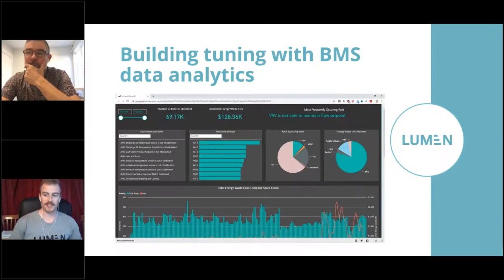In a slightly more complex case, the rule could ask, is the air temperature rising over a heating coil when the heating coil is supposed to be shut? So like we were talking about before. If so, let me know that it's happening. We can input data around the size of the system in there so it can tell us roughly how much it's costing us. And then we can make a decision to go out and fix it.